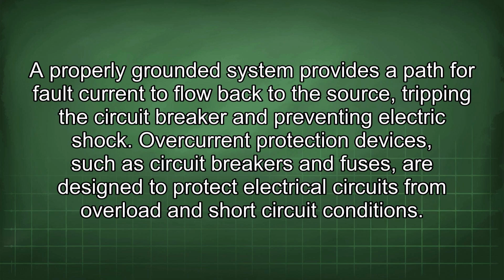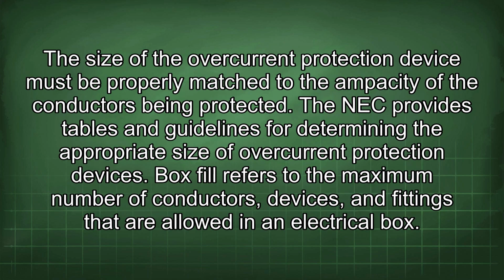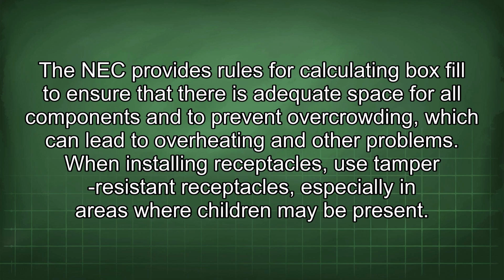A properly grounded system provides a path for fault current to flow back to the source, tripping the circuit breaker and preventing electric shock. Overcurrent protection devices, such as circuit breakers and fuses, are designed to protect electrical circuits from overload and short-circuit conditions. The size of the overcurrent protection device must be properly matched to the ampacity of the conductors being protected. The NEC provides tables and guidelines for determining the appropriate size of overcurrent protection devices. Box fill refers to the maximum number of conductors, devices, and fittings that are allowed in an electrical box. The NEC provides rules for calculating box fill to ensure that there is adequate space for all components and to prevent overcrowding, which can lead to overheating and other problems.